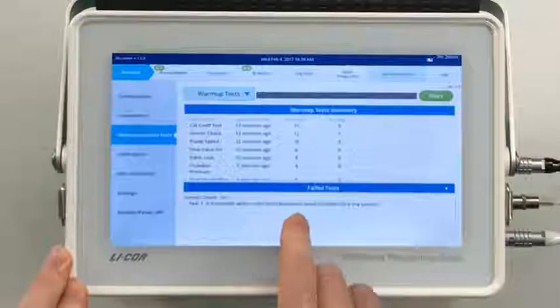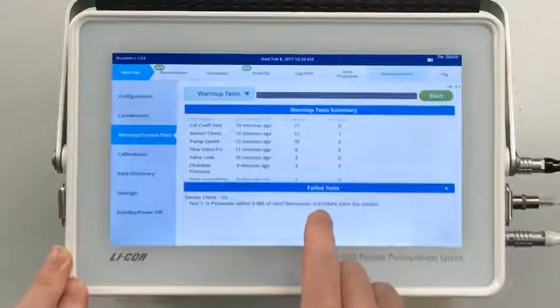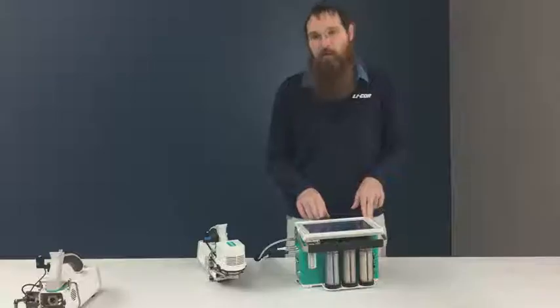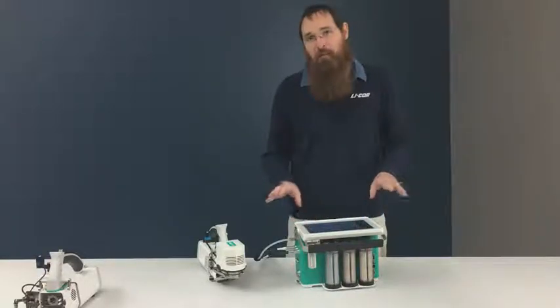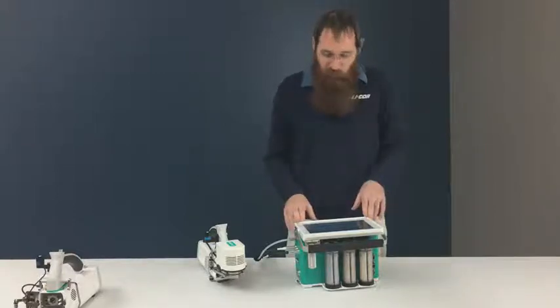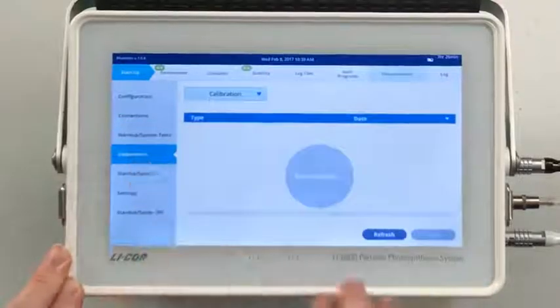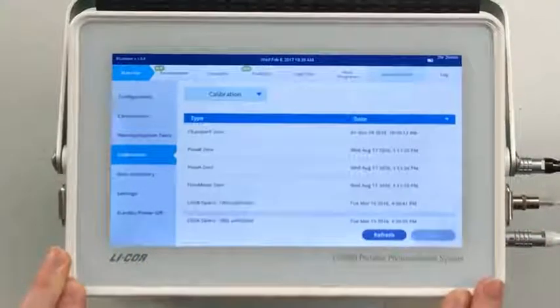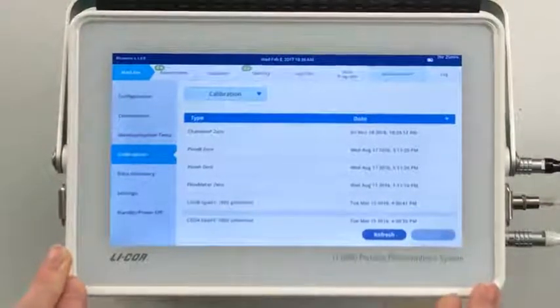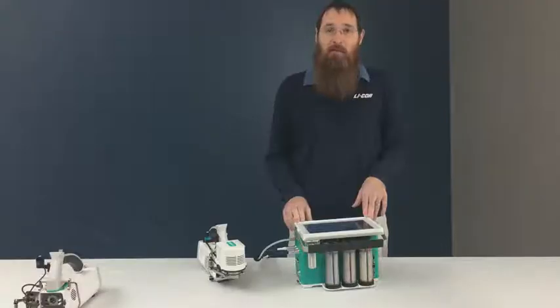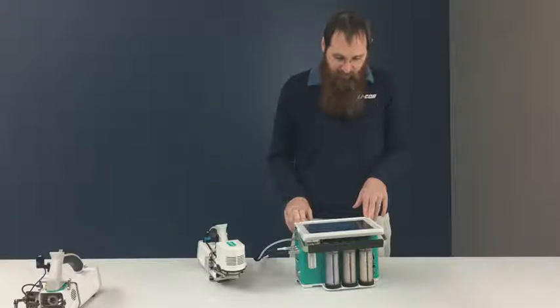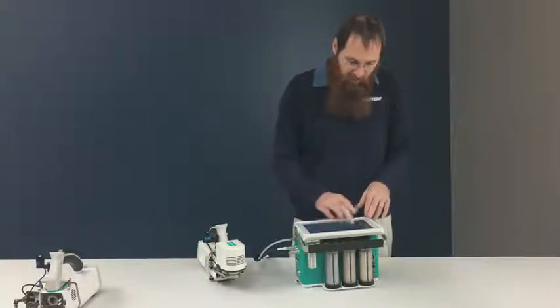It says, is P chamber within 0.005 of 0? And it measured it at minus 0.019. All right, that's a fairly small offset. I'm not particularly worried about it in the context of what we're doing today, but if I were going to actually make measurements with this instrument, I would go to this calibration screen and pull up the console that lets me adjust the P chamber calibration, and I would zero the pressure sensor. And that would be my full checkout before I took it in the field. All right. That's what I want to say about the startup panel.